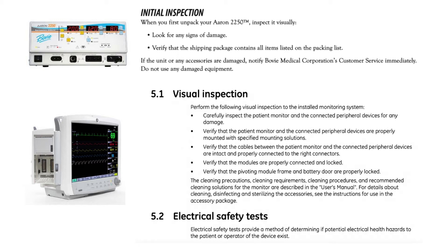Different service manuals provide different levels of detail for the inspection. Bovie Aaron 2250 provides very little — it just says look for signs of damage. Whereas GE Carescape's visual inspection includes a variety of bullet points, some of which require you to check that things are locked properly, modules are connected, and things are pivoting properly. In most manuals, you'll see that the inspection precedes the electrical safety tests.